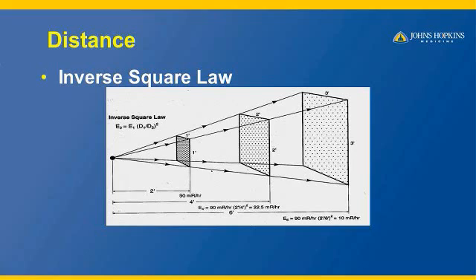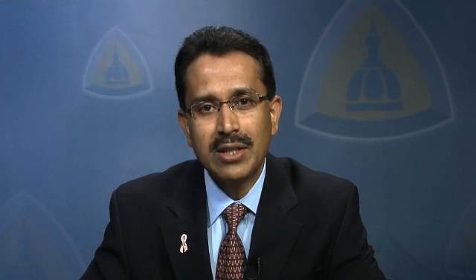The second pillar of radiation protection is distance. Distance works to our advantage in any x-ray room or in front of any x-ray source, because the further away you stand from the x-ray source, the less scatter one gets. The scattered radiation coming out is in all directions, therefore we need to understand the distribution of scattered radiation to protect ourselves in a medical x-ray room.